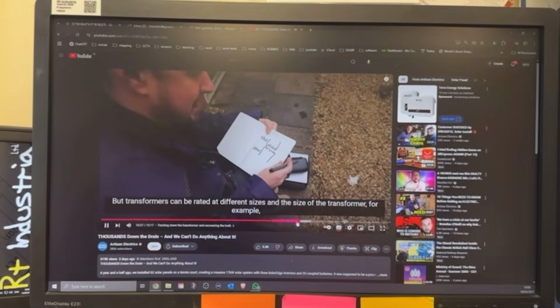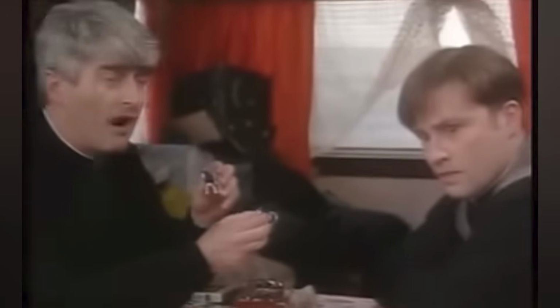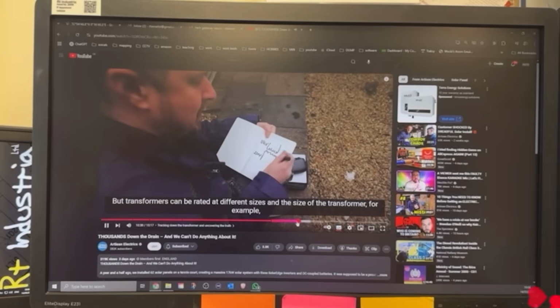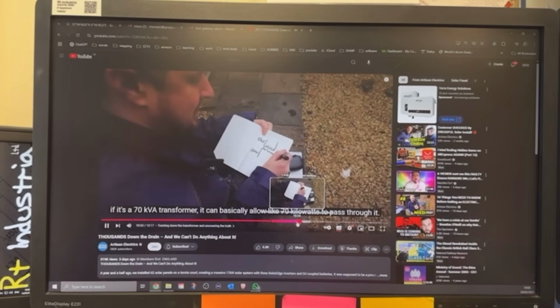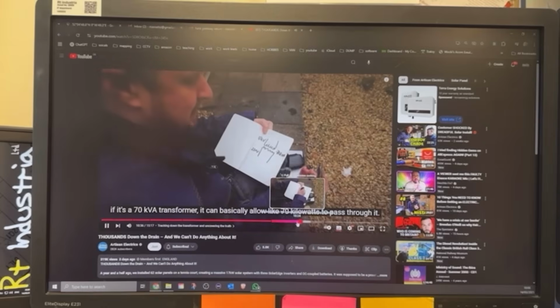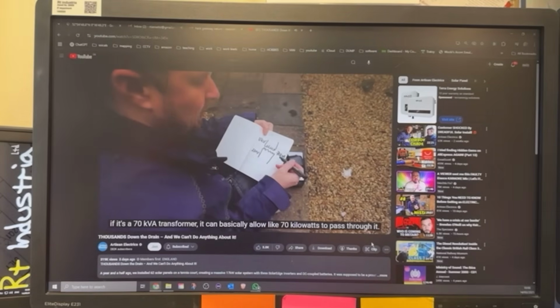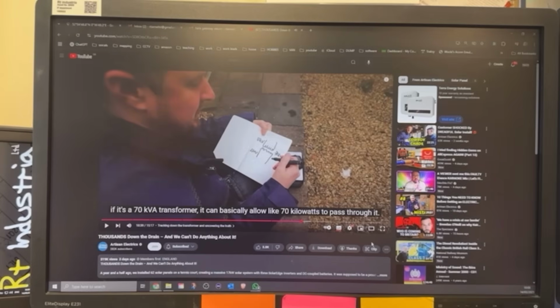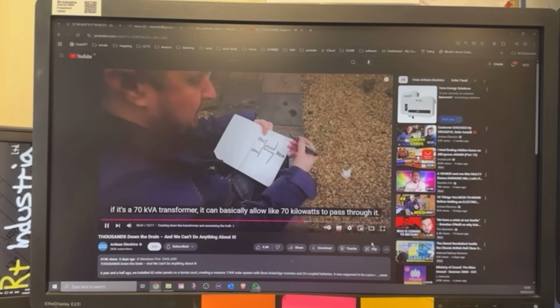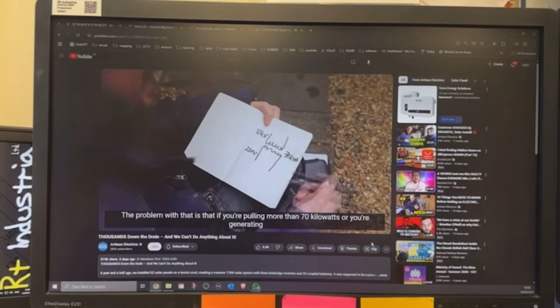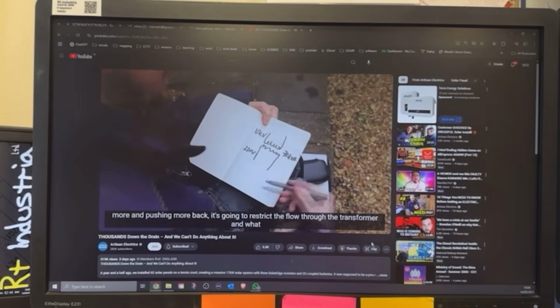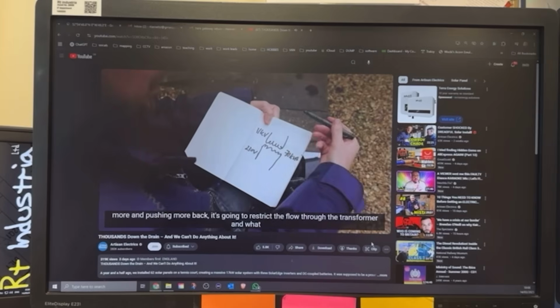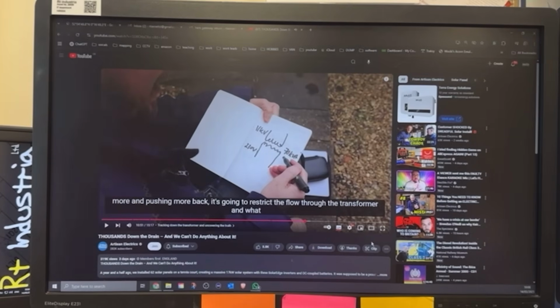Transformers can be rated at different sizes. These are small, but the ones out there are bigger. The size of the transformer - for example, if it's a 70 kVA transformer, it can basically allow about 70 kilowatts through it. Not quite right, but yeah, close enough for civilians. The problem is that if you're pulling more than 70 kilowatts, or generating and pushing more back, it's going to restrict the flow through the transformer. But a transformer is not a restriction device - a transformer is a winding, and it has protection either side of it in the form of fuses.